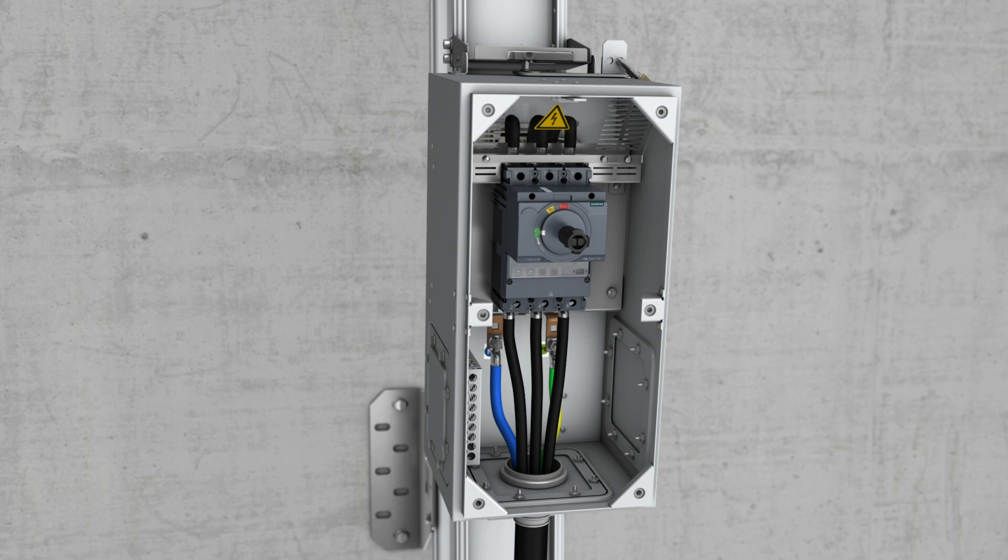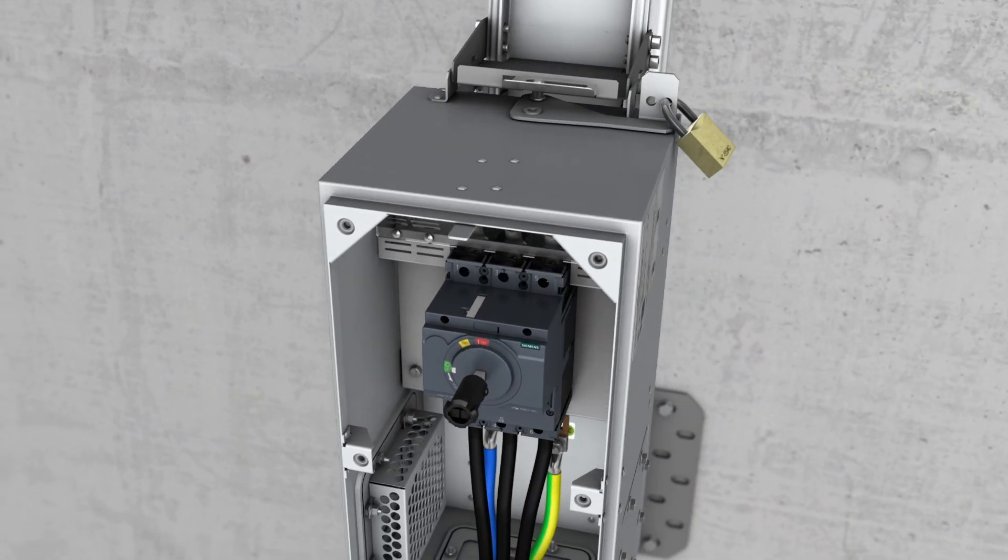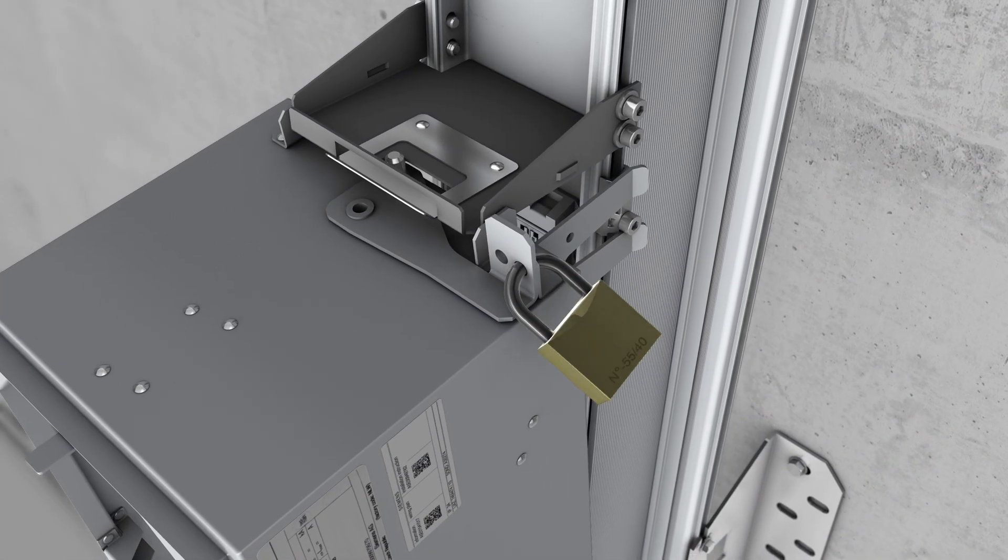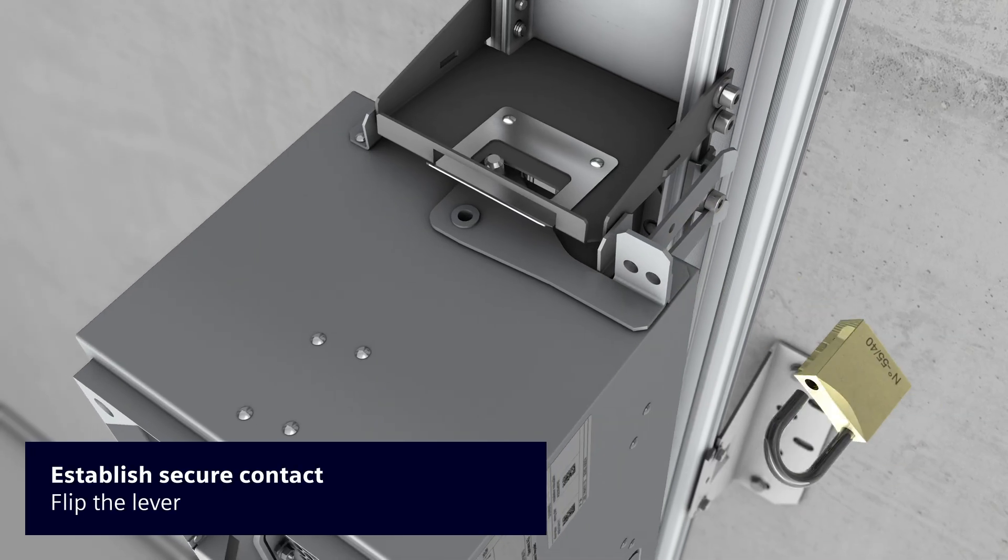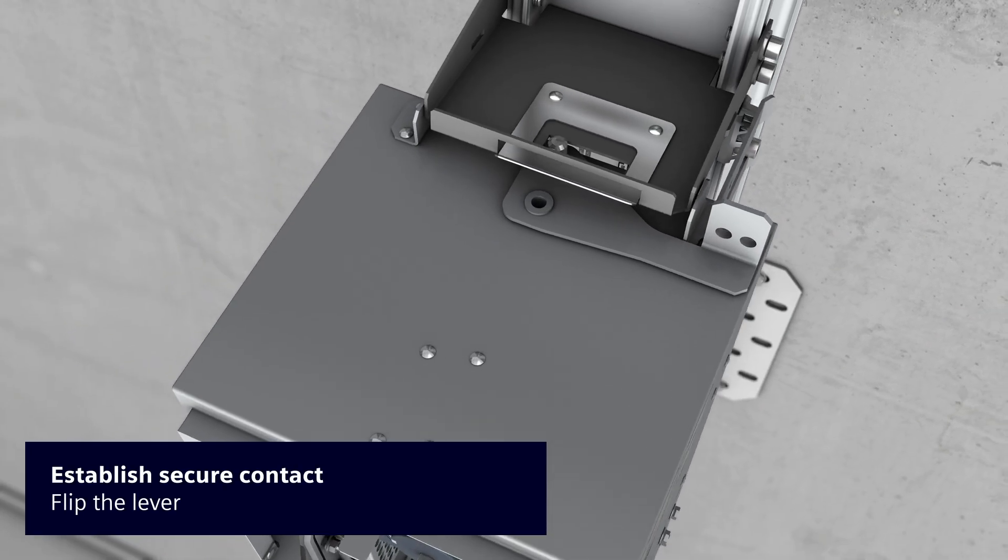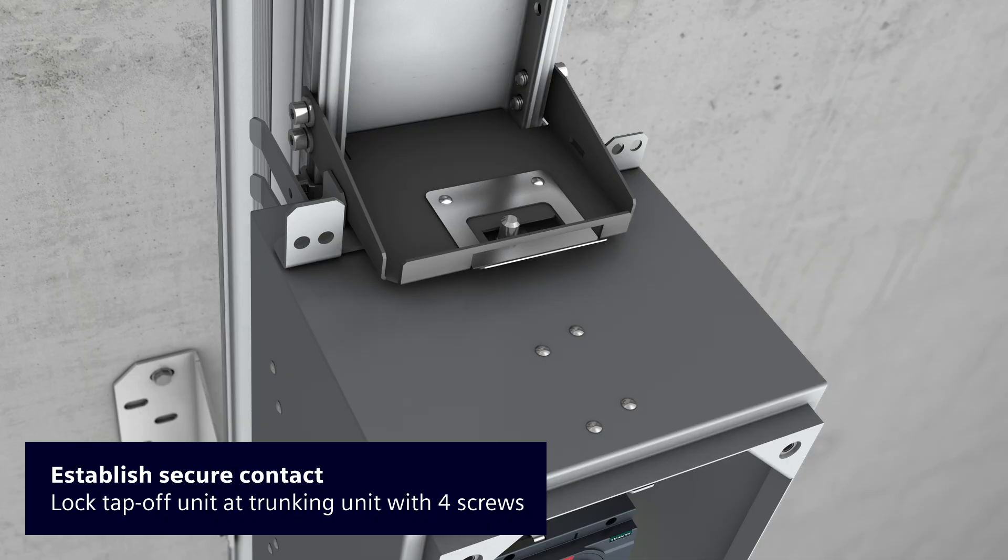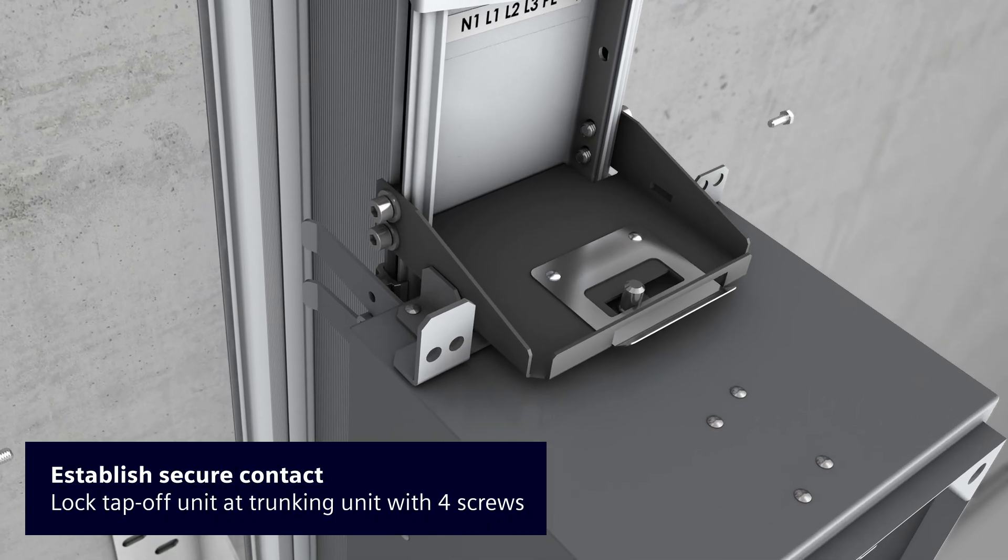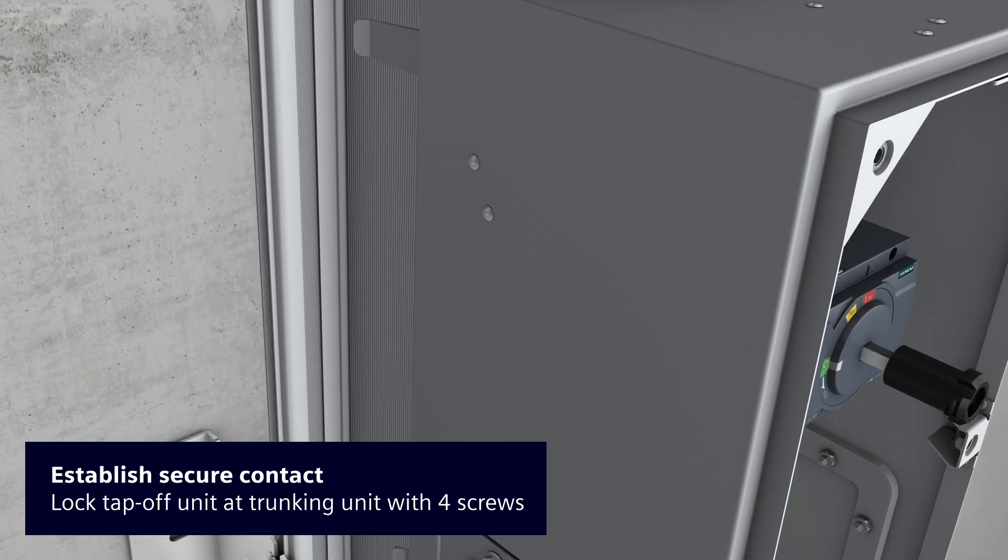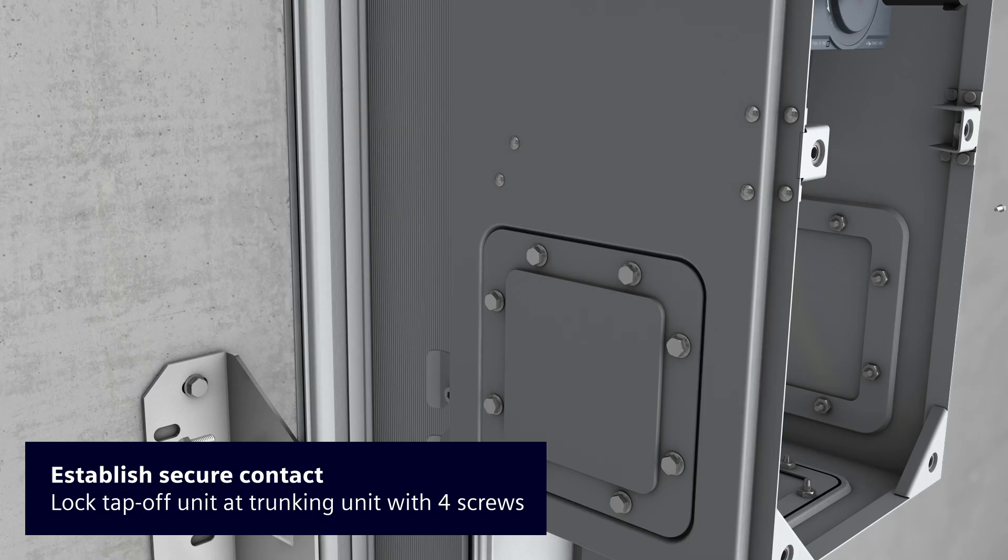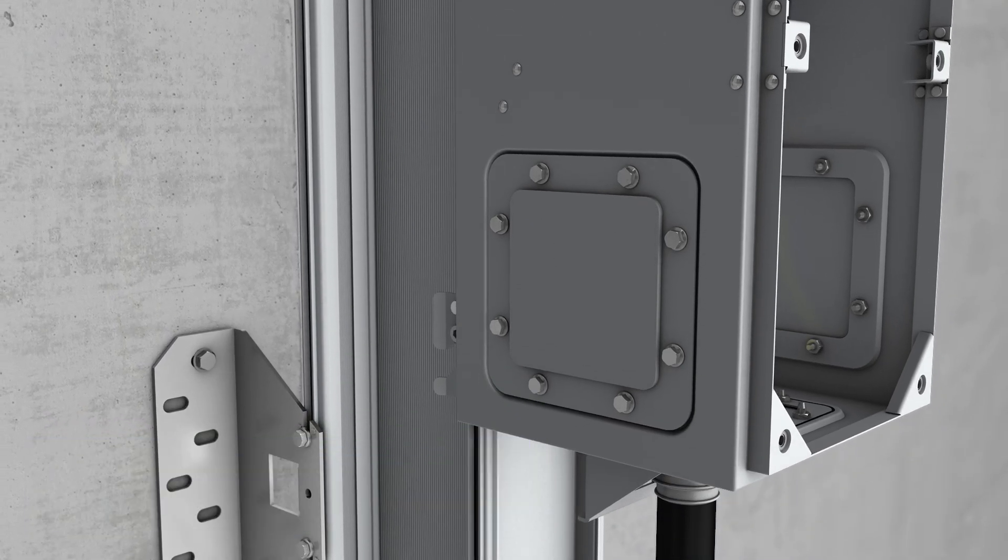Electric contact between the tap-off unit and the bus bar system must not be established before all cable connections have been completed and secured. Where used, remove the optional lock from the lever and then move the lever to its end position. This action will pull the unit to the bus bar and establish the electric connection with the trunking system.